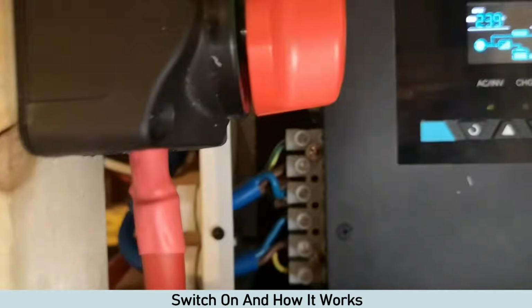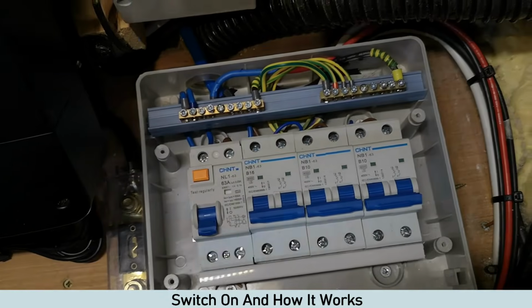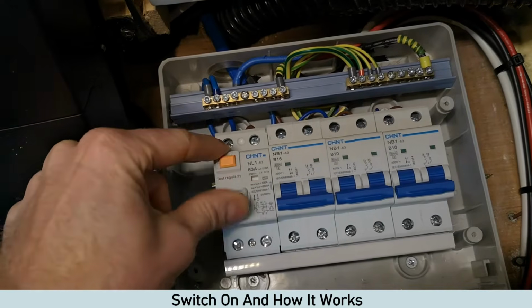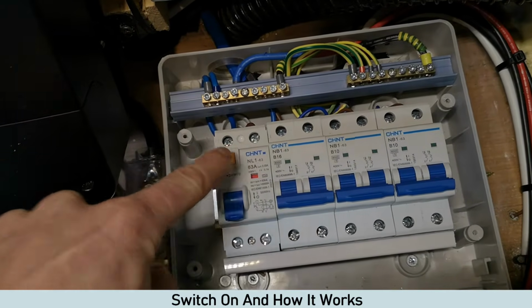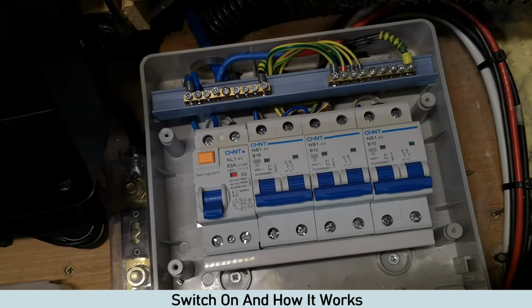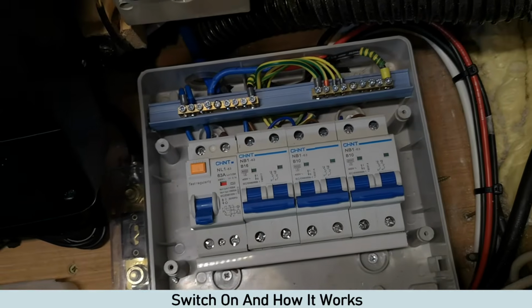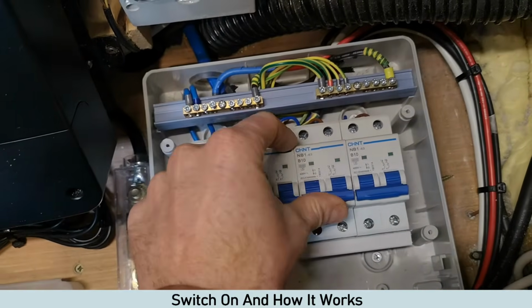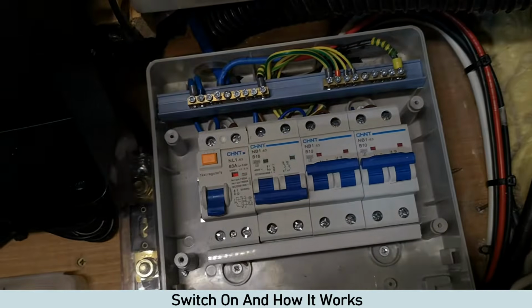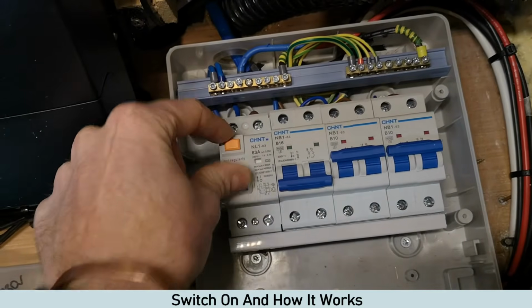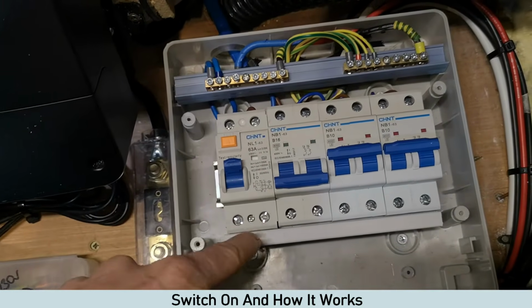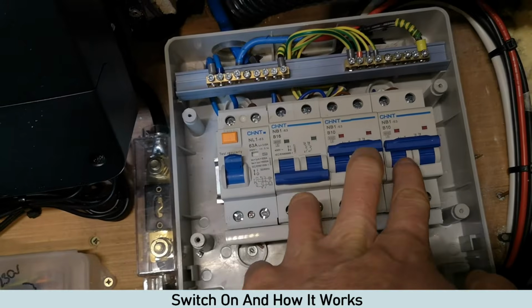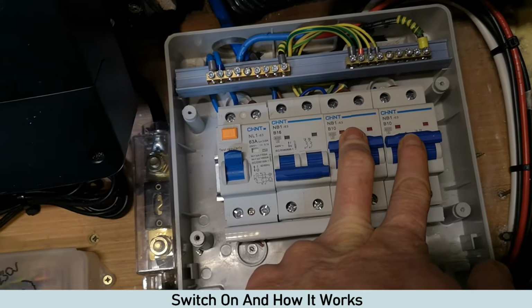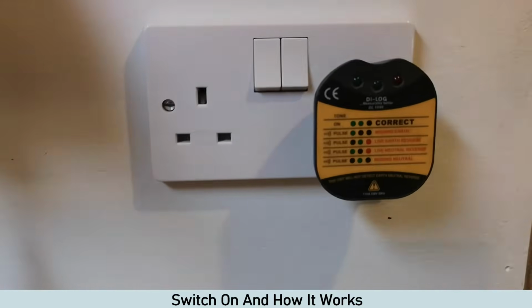So what's happening now is power's going out of here. It's coming into here, and then the RCD, as you can see, is tripping. Happy days. So if I switch on, I can't remember which circuit it is, but I'll do both of these. So RCD's on, power's then running through here, and it's going to these two socket circuits. So here's the socket, and I've got a socket tester plugged in.